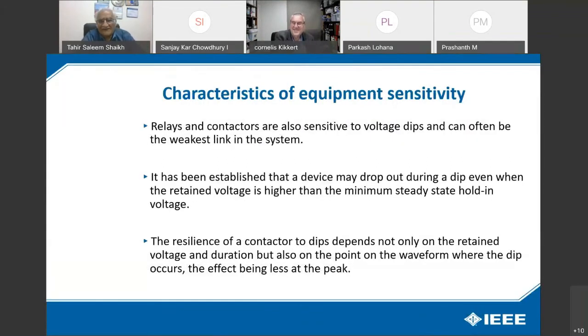Relays and contactors are very sensitive to voltage dips and can often be the weakest link in the system. It has been established that a device may drop out during a dip even when the retained voltage is higher than the minimum steady state hold-in voltage. The resilience of the contactor to a dip depends not only on the retained voltage and duration, but also on the point on the waveform where the dip occurs, the effect being less at the peak.